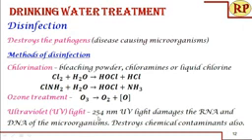But in ultraviolet, there's another advantage, that is, some of the microorganisms, especially the protozoans, are not destroyed by chlorination. That is, even chlorine resistant microorganisms like protozoans can be easily destroyed by ultraviolet light. And another advantage is some of the pollutants. We haven't mentioned those pollutants, assuming that the water is not polluted, but the surface waters can be polluted by industrial waste like industrial solvents, pesticides, that is from your agricultural waste, and you can have some pharmaceutical waste also. All these wastes also can be destroyed using ultraviolet light, so it's more preferable.